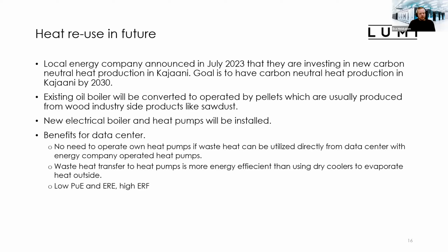And my opinion is that waste heat transfer to the heat pumps is more energy efficient than using the dry coolers to evaporate heat outside. But this is something where maybe we could make some calculations in our current installation, on how much energy we are using only to transfer this heat load to the district heating, compared to when we are running it on free cooling. So this would be something that could be investigated a bit further. But this will end up with a low PUE, low ERE, and high ERF value.